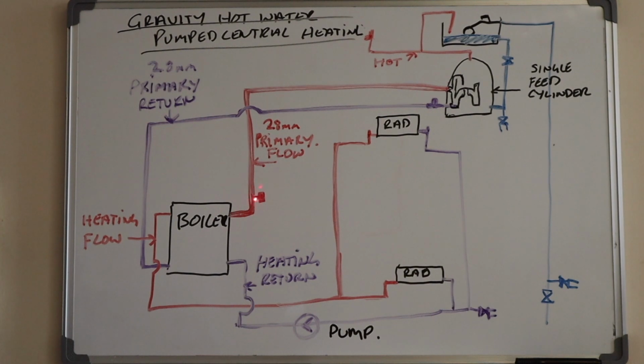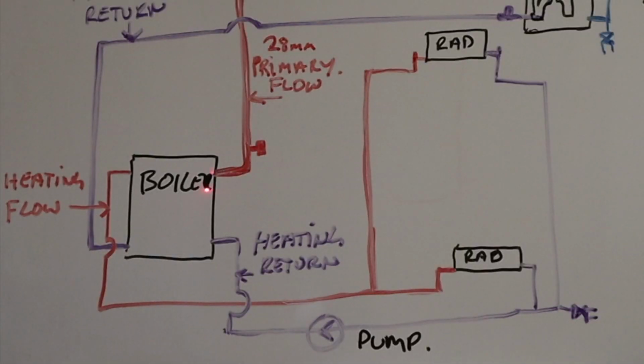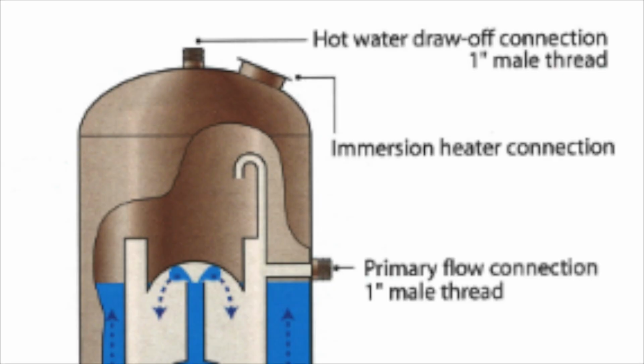Now we said we had the relief valve. Again, if anything happens with the PRIMATIC, because we've got the PRIMATIC cylinder here, then this would start to drip. And you should be able to find these on back boilers and stuff like that. So if we look at the heating circuit, we can see this is the flow pipe. But there's no pump on the flow in this system because it's gravity hot water pumped central heating. They used to put the pump on the return.